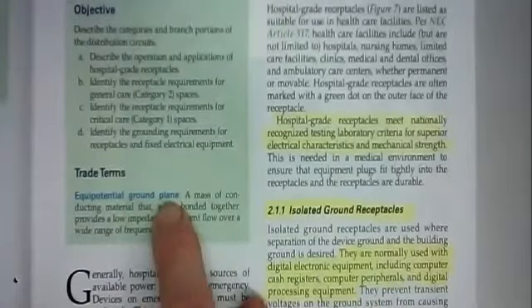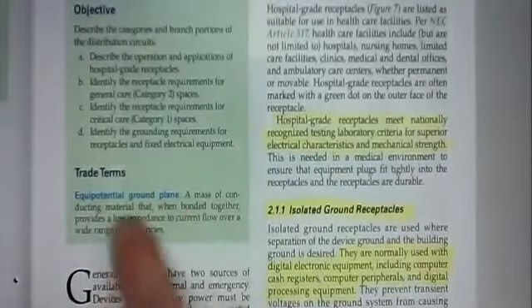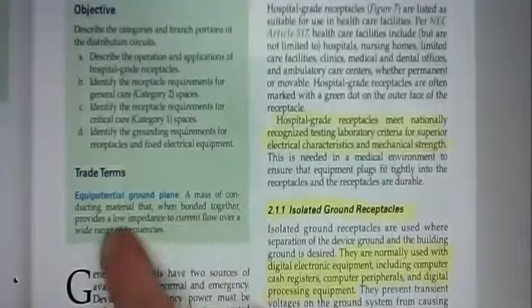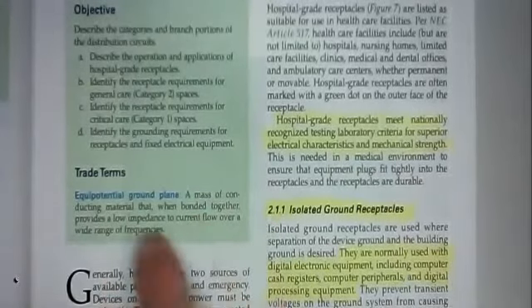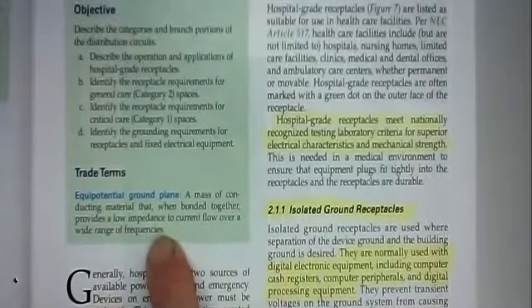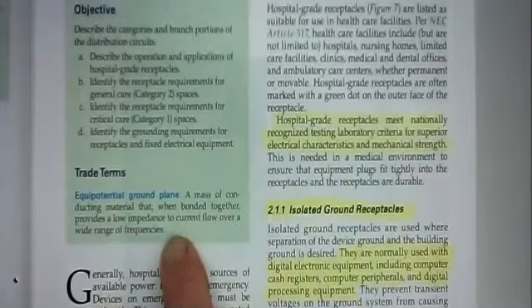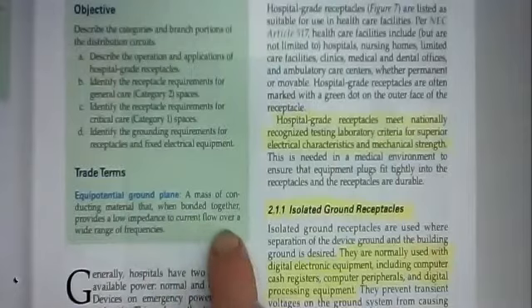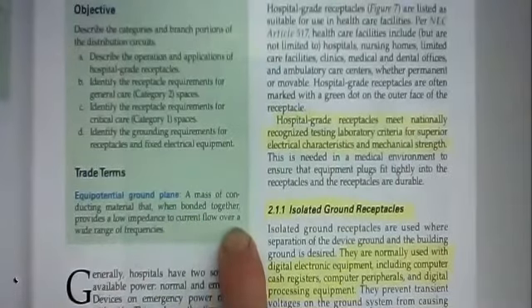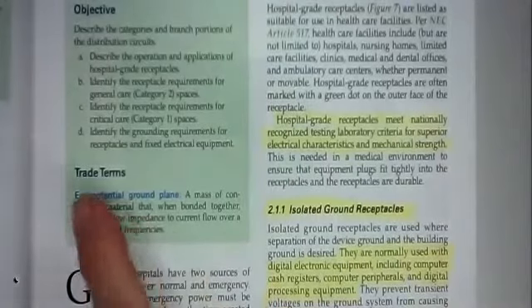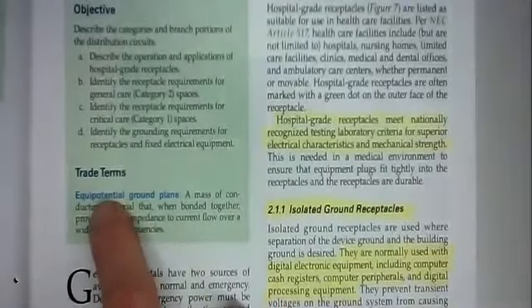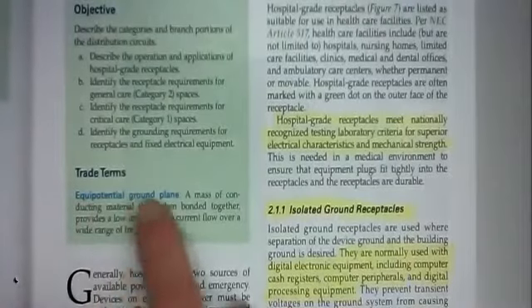Well, this is talking about patient care areas, a mass of conducting materials that, when bonded together, provide a low impedance to current flow over a wide range of frequencies. So everything in your hospital room is tied together. You don't see it, it's in the walls, but they've got a minimum of a number 10 conductor that runs around to all the receptacles. It sticks out for the bed. It sticks out, it ties into the sink. It goes into the emergency panel and the regular power panel so that everything in that room is at the same potential, voltage, potential, equal voltage, equipotential plane.